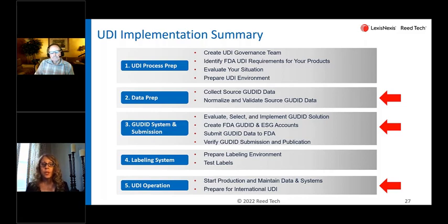So additionally, what we're going to do is help you to set up your health authority account, and in this case, setting up a GUDID account for the FDA. That requires some tests, and once you've done all that and you're ready, then we can help you electronically submit that information using an ESG, which is an electronic submission gateway, and submit that to the FDA. This again saves a great deal of time, rather than, like Gary said, many might be doing this with manual entry.